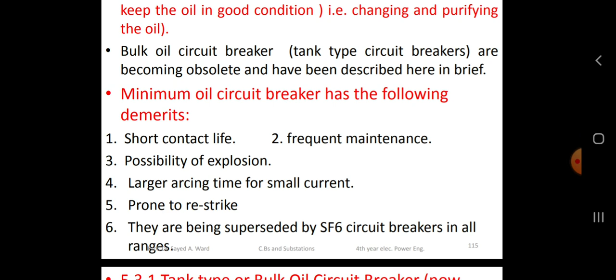Tank type or bulk oil circuit breakers. Bulk oil circuit breakers are enclosed in metal grounded weatherproof tanks that are referred to as dead tanks. The tank type circuit breakers had three separate tanks for 72.5 kV and above, and a single tank for 36 kV and below. In single tank construction, phase barriers were provided between the phases. The contact separation takes place in the steel tank.